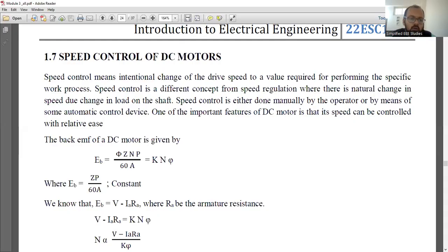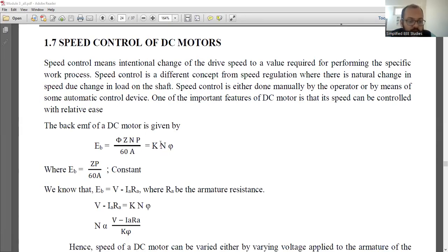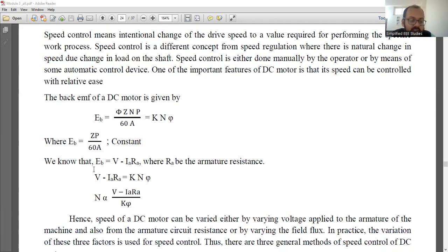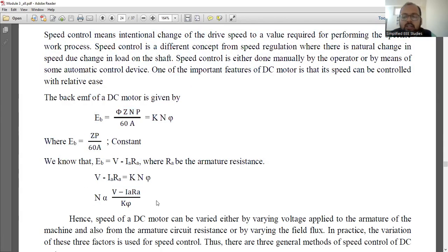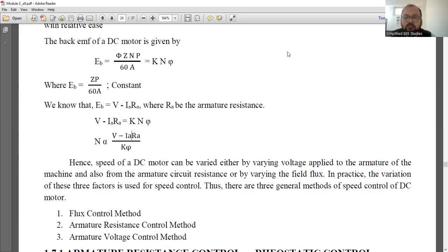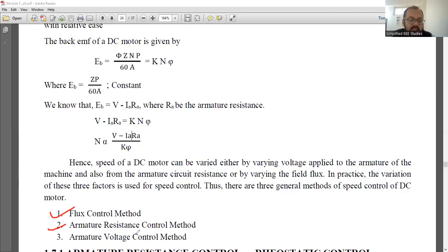Let me show you the speed control methods. Whenever you want to explain the speed control of a DC motor, try to write the equation: N is proportional to Eb/φ. From this, you can explain speed control of both DC motors very easily. For the shunt motor speed control, the popular methods are: flux control method, armature resistance control method, and armature voltage method. If you want above-rated speed, go for flux control. If you want below-rated speed, go for armature resistance control method.